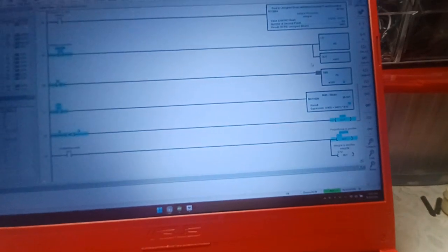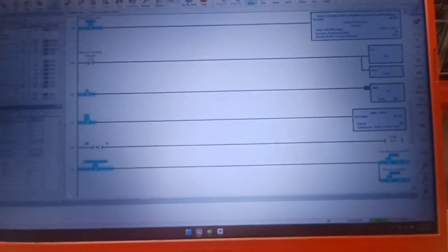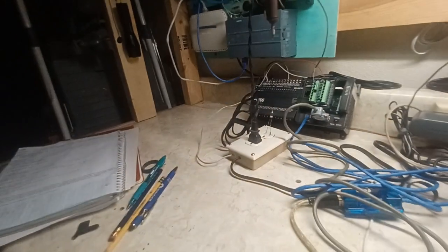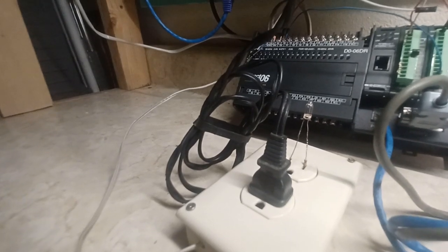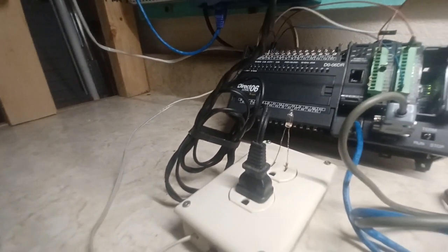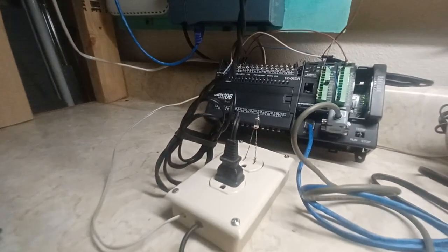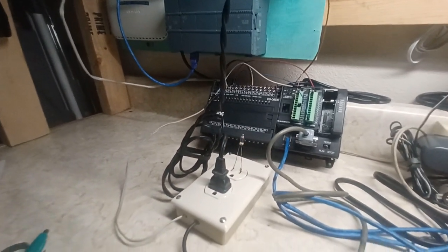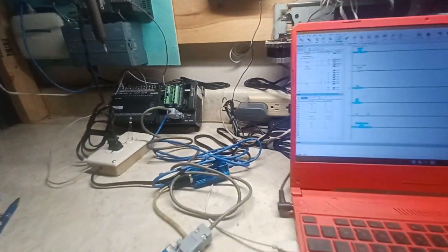timer. I have a timer here that is about 10 seconds. So the duty cycle on the timer is what turns on that output. If you see that neon light bulb, that is the output going on and off. That indicates when the output is turned on. So that's the duty cycle. It's converting PID into duty cycle.